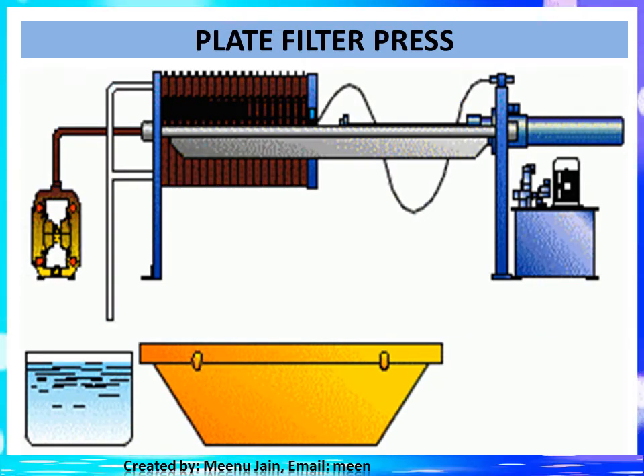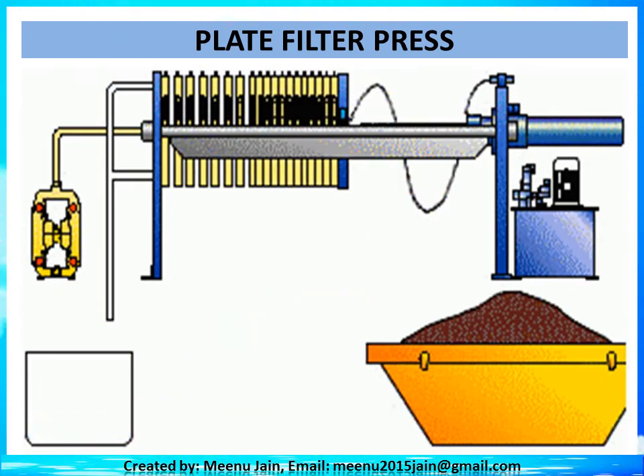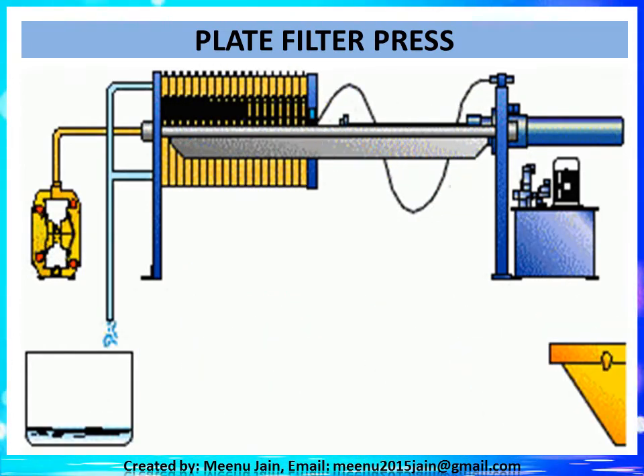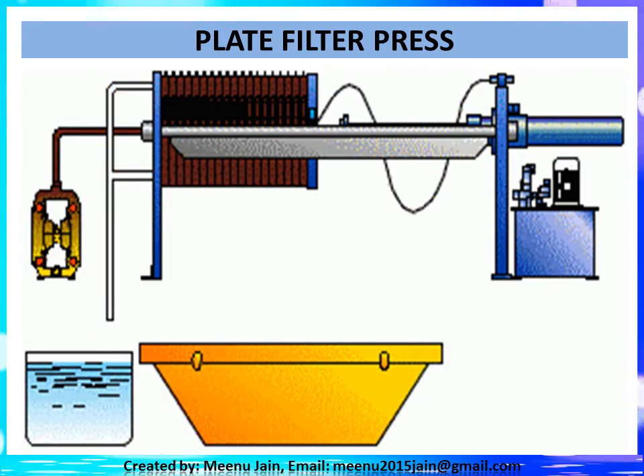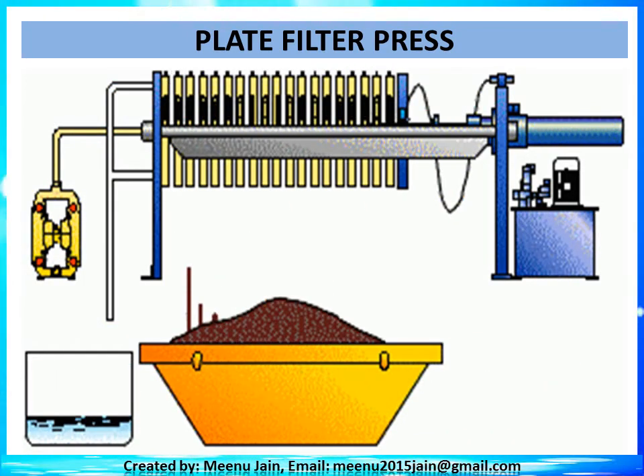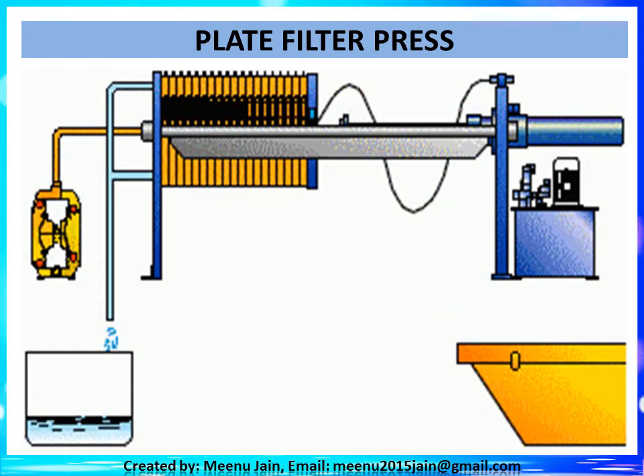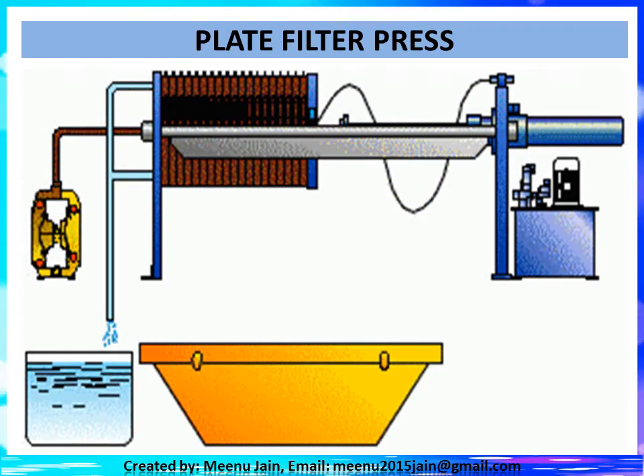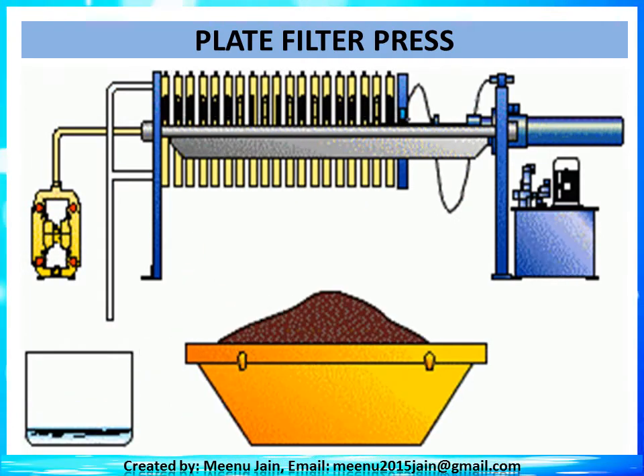The next sludge dewatering unit is the filter press. Dewatering is achieved by forcing water from sludge under high pressure. Chemically conditioned sludge is pumped into spaces between plates, and pressure of 690 to 1550 kN/m² is applied and maintained for 1 to 3 hours, forcing liquid through the filter cloth and plate outlet ports. Sludge cake thickness varies from 25 to 38 mm, moisture content from 48 to 70%, and filtration cycle from 2 to 5 hours. High cake solid concentration with good filtrate quality and high solid capture is achieved, but mechanical complexity, high chemical cost, high labor cost, and limitations on filter cloth life are disadvantages.